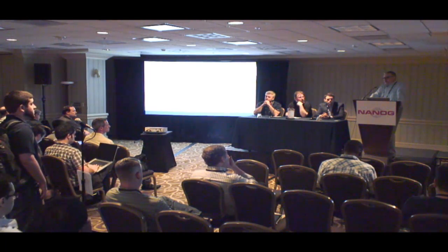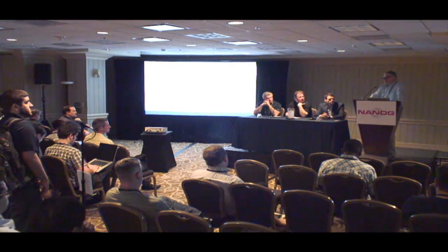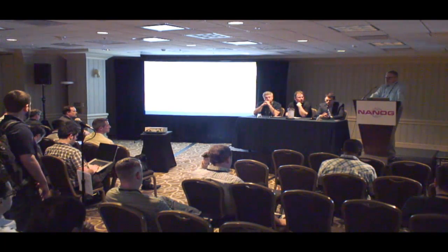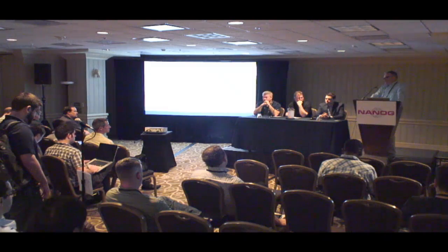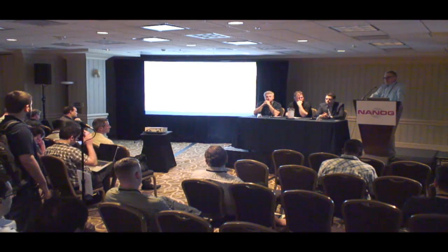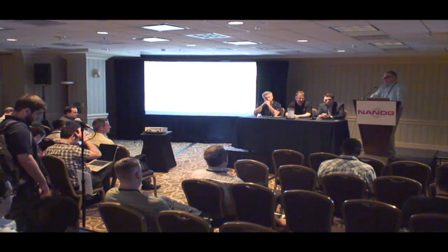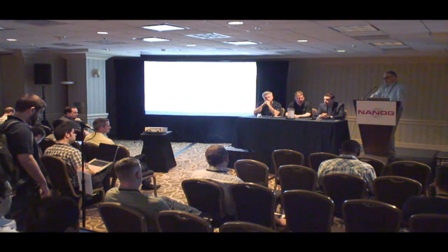Most of the 480 you're going to see is going to be in the newer data centers, and it is the real thing. When you're dealing with 4160 on the high side and 480, you're talking about linemen more than you're talking about electricians. You're talking about people that have years of training, either military or working for a utility, that are comfortable and know how to work with those higher voltages.